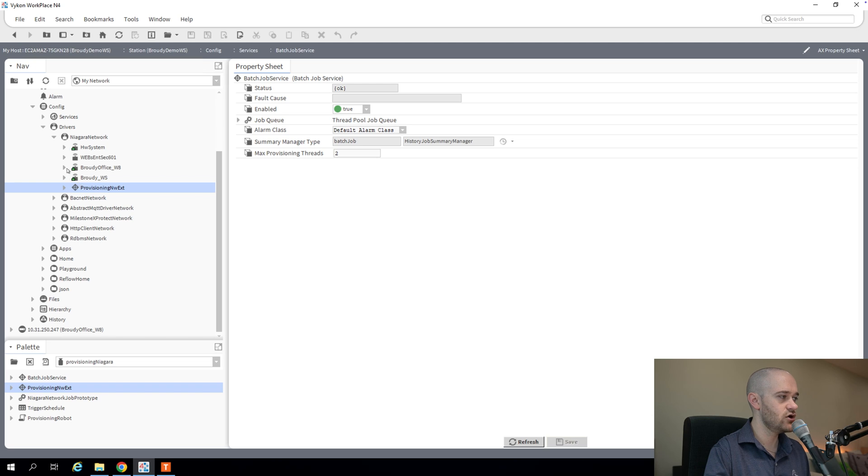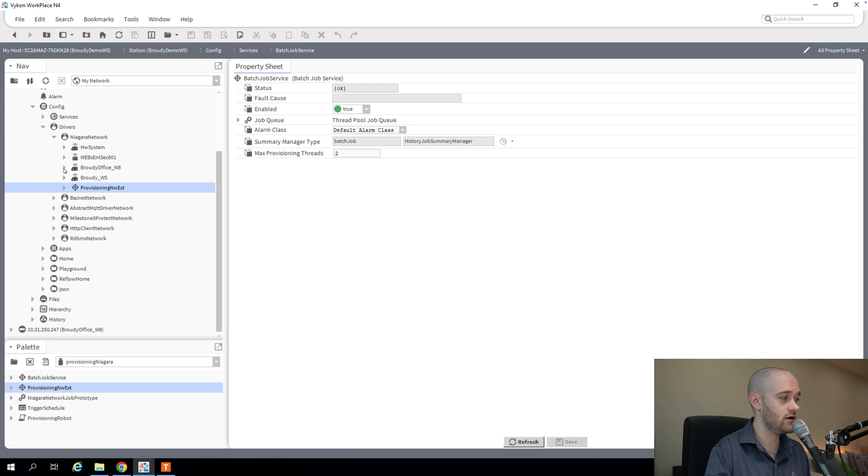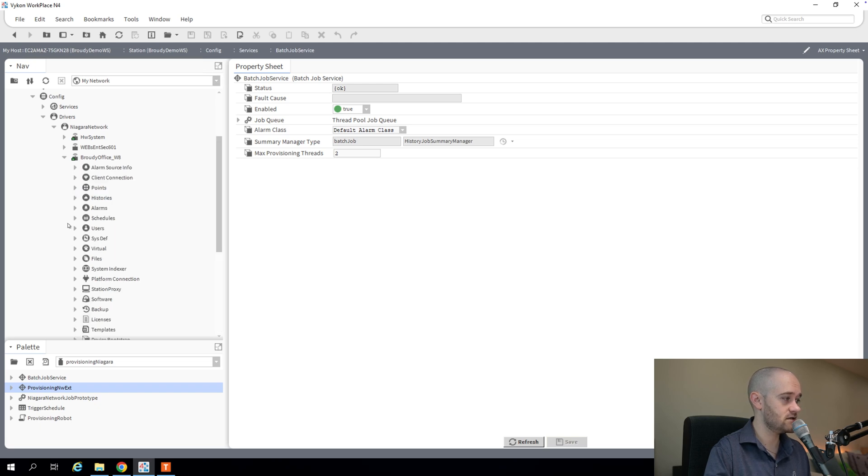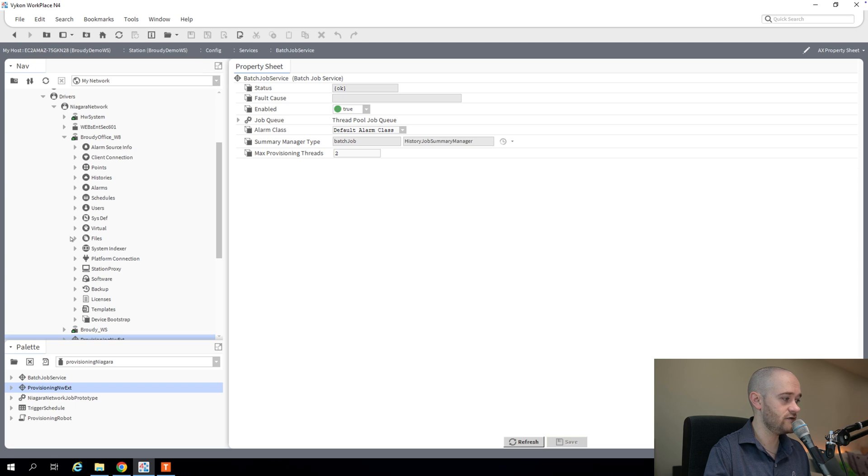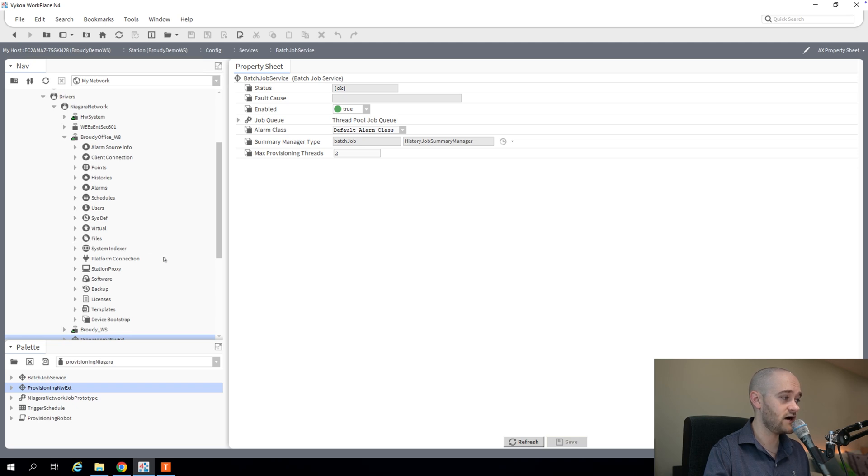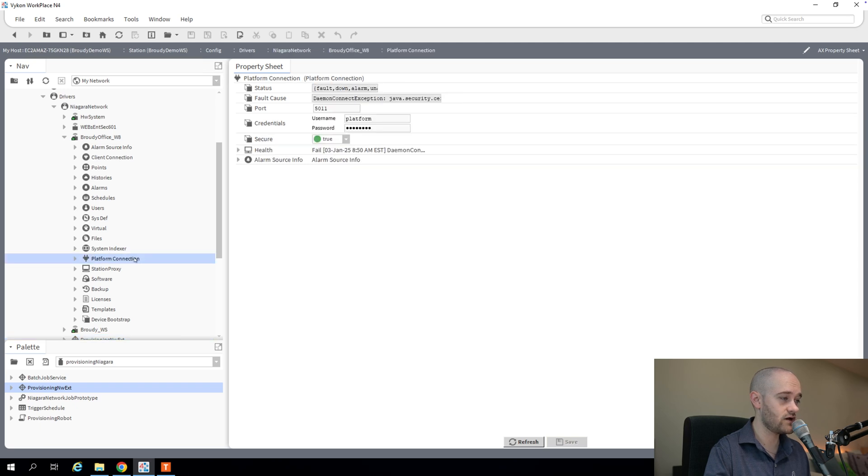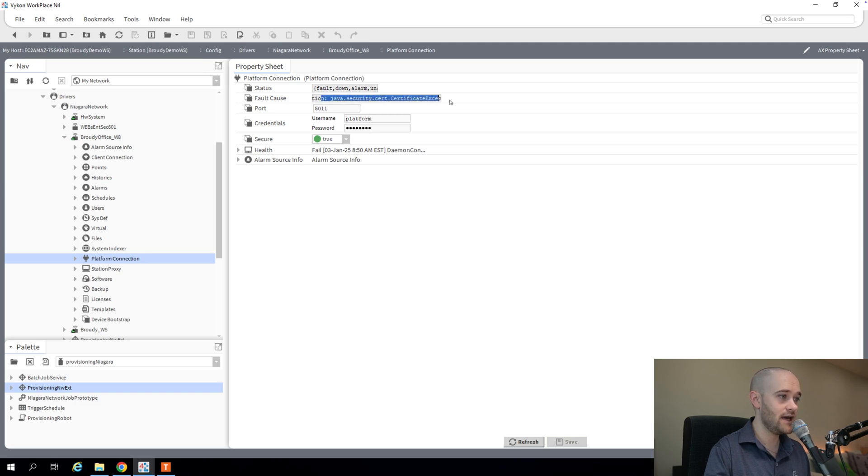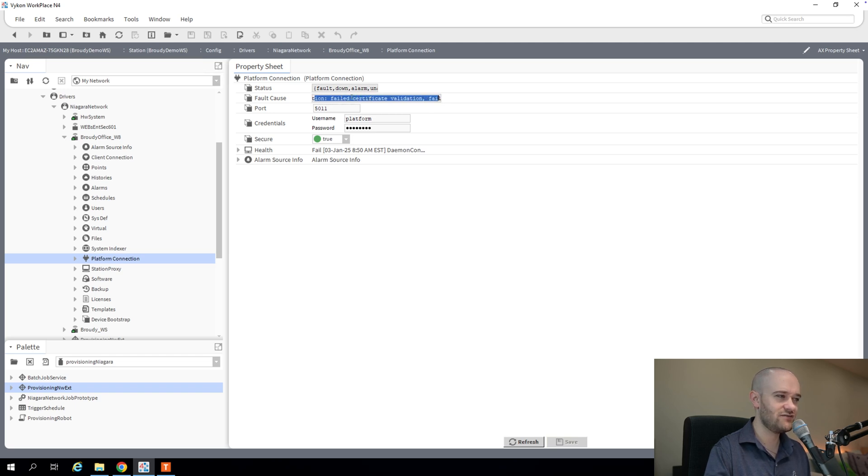Next, we're going to expand one of our jaces that we want to provision. And the way provisioning works, it actually makes use of the platform connection as well as your Fox connections to your individual jaces. So you want to make sure that your platform connection is set up and working properly. And you can see for mine, I've got the username and password in here, but I'm getting an error message. If you've done any of this stuff a bunch of times, you've probably run into this error message.